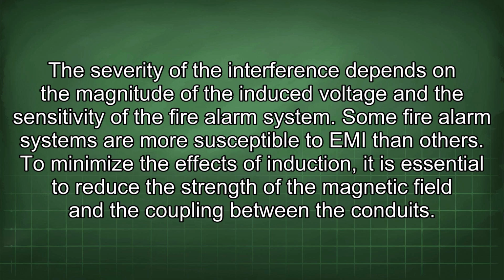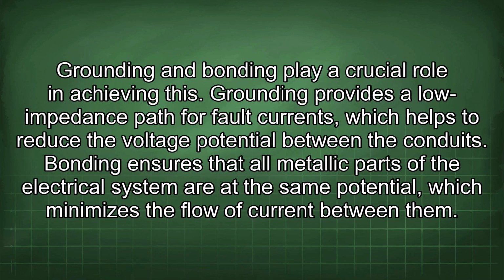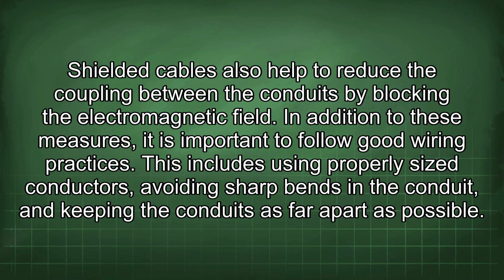To minimize the effects of induction, it is essential to reduce the strength of the magnetic field and the coupling between the conduits. Grounding and bonding play a crucial role in achieving this. Grounding provides a low impedance path for fault currents, which helps to reduce the voltage potential between the conduits. Bonding ensures that all metallic parts of the electrical system are at the same potential, which minimizes the flow of current between them. Shielded cables also help to reduce the coupling between the conduits by blocking the electromagnetic field.